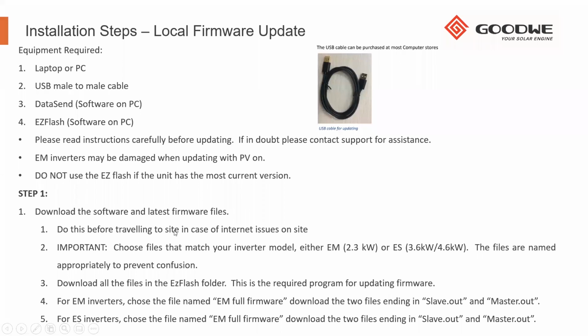So if you contact our support or your distributors for support, they should supply you with a download link for the latest firmware files. So you can always download these. The link that they should send you will always be a live link and always contain the latest firmware. So before you go to site, you just download it again, and make sure that when you get to site, you have everything with you. It's very important to make sure you use the correct firmware for the correct inverter.